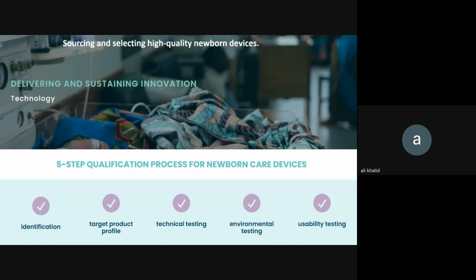The manufacturer says it gives 93% pure oxygen. We do tests with various testing equipment to make sure that this is what the manufacturer has written or said, and this is what we actually get. We do the electrical safety test and all those. Then if it passes that, it goes to the next stage of environmental testing. This involves putting the device in a dust chamber where it is exposed to dust, high humidity, low humidity, high temperatures, low temperatures, to simulate the tropical settings that you find in Africa, so that these devices are rugged and robust and don't break easily or get affected by the slightest environmental issues like humidity and temperature changes.